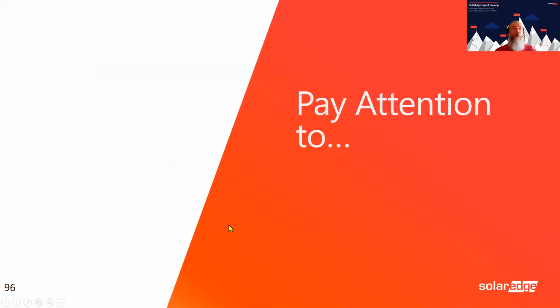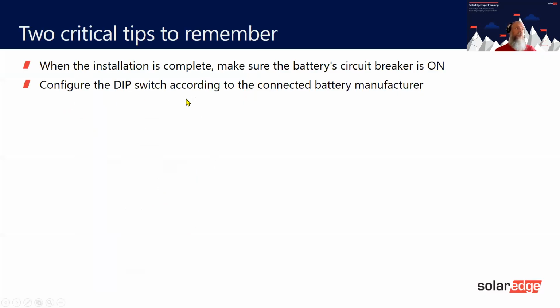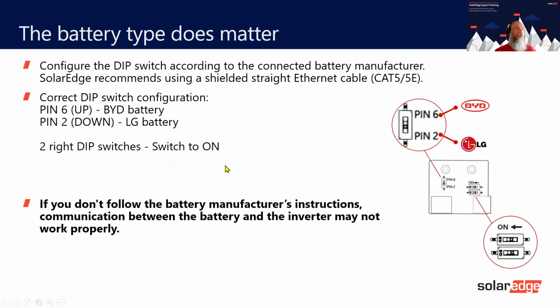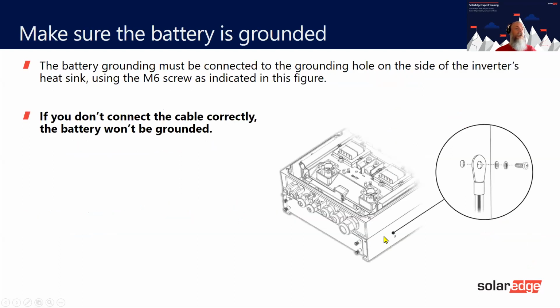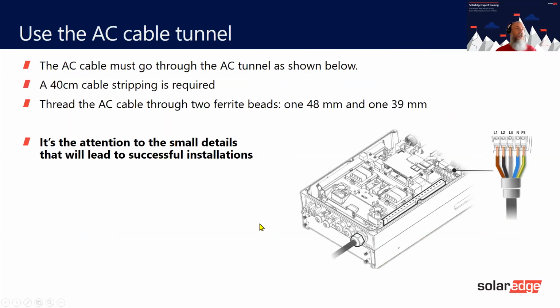So what should I pay attention to? Well, make sure the dip switches are according to the connected battery. Remember, BYD and LG had a different position on this switch here. So pay attention to that one. You need to ground the inverter as well on the outside. And obviously, you don't want any mechanical stress or tension on these connections. So make sure you use the channel and make sure you have adequate gaps, basically length of cable, going into here. You don't want these pulling, okay?